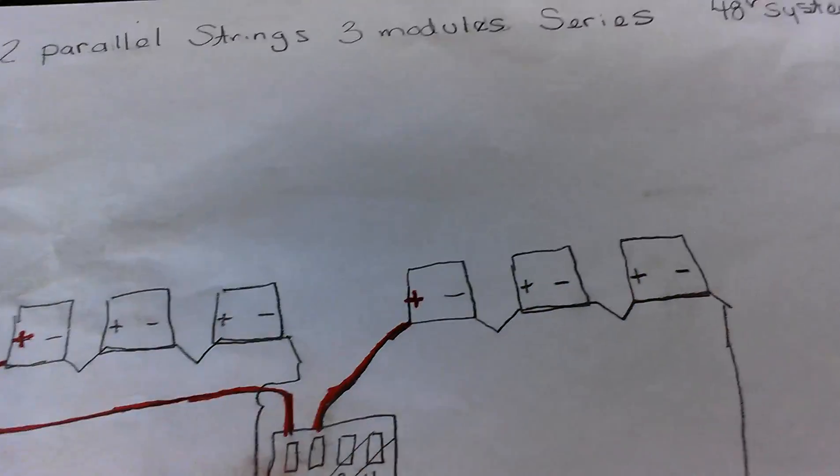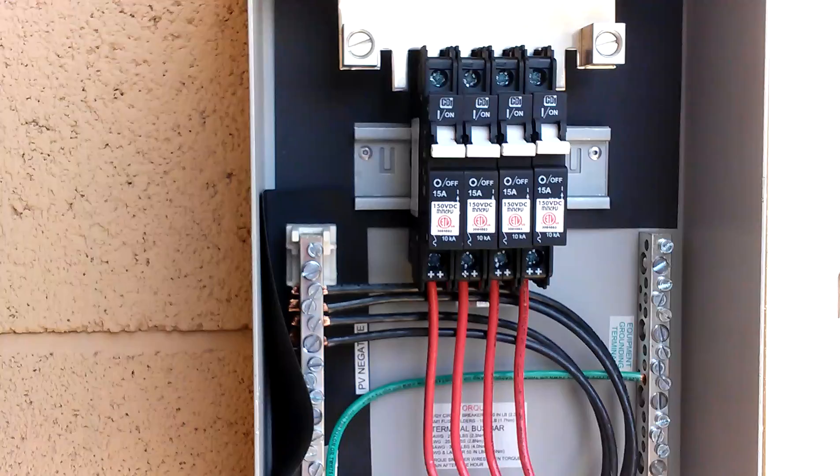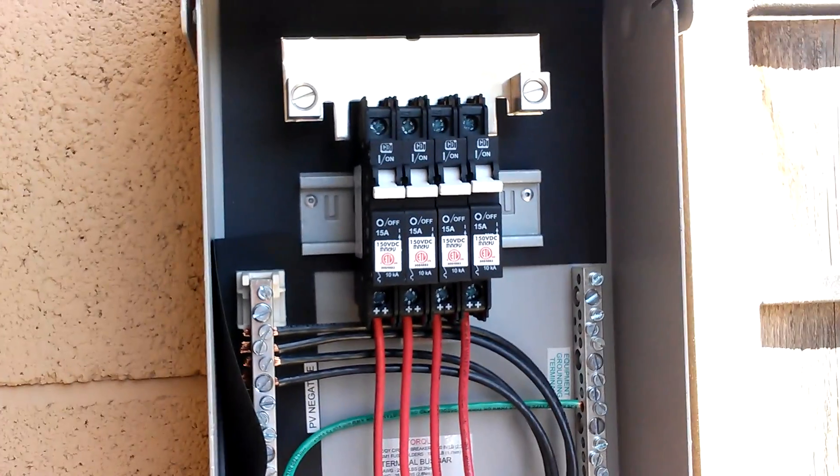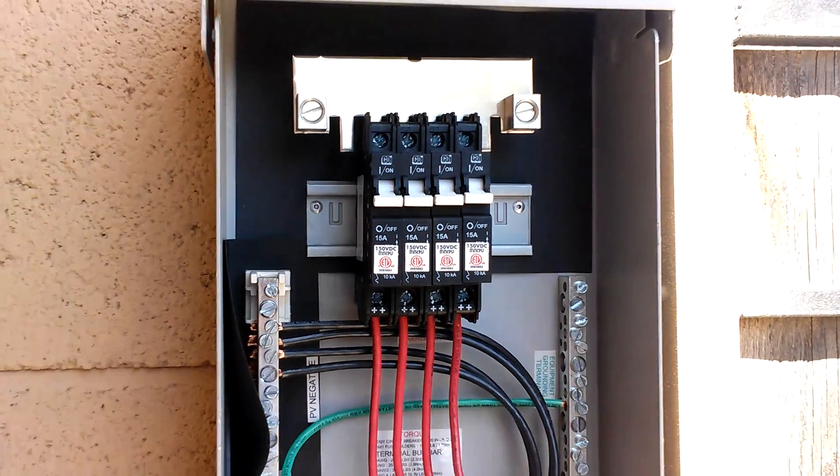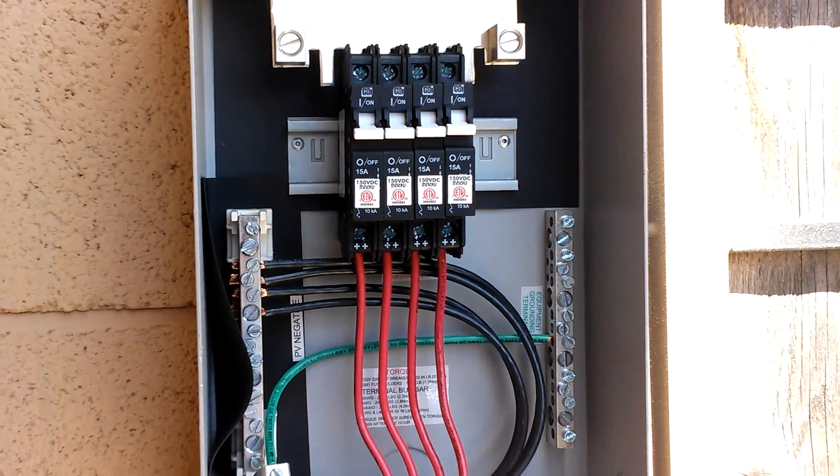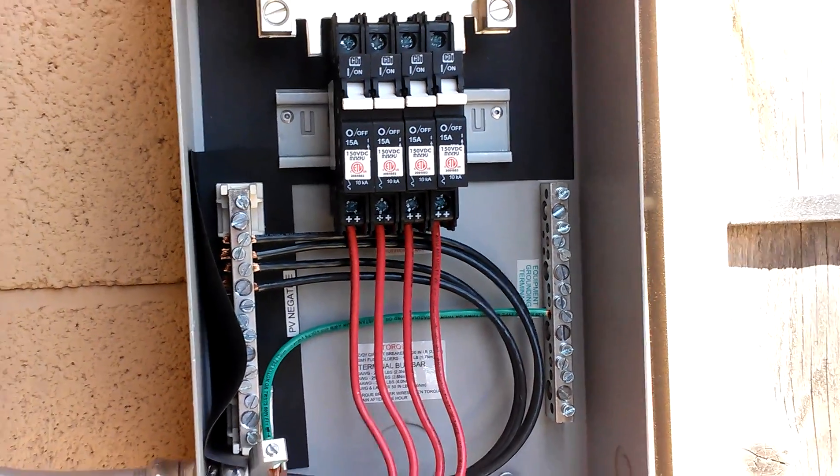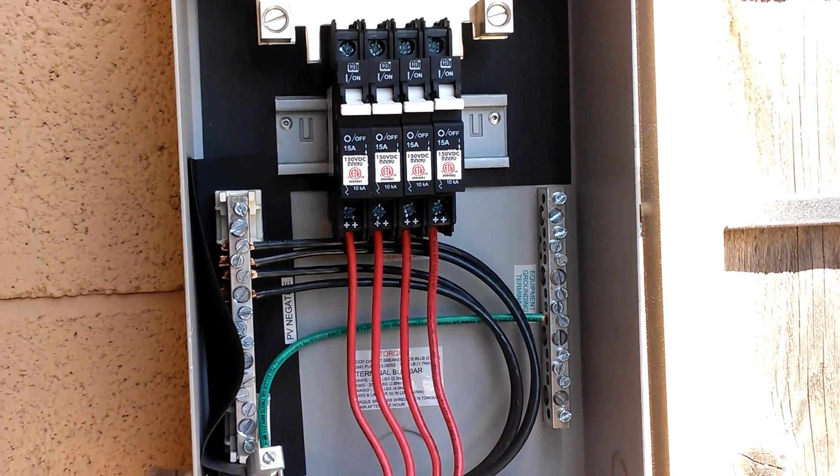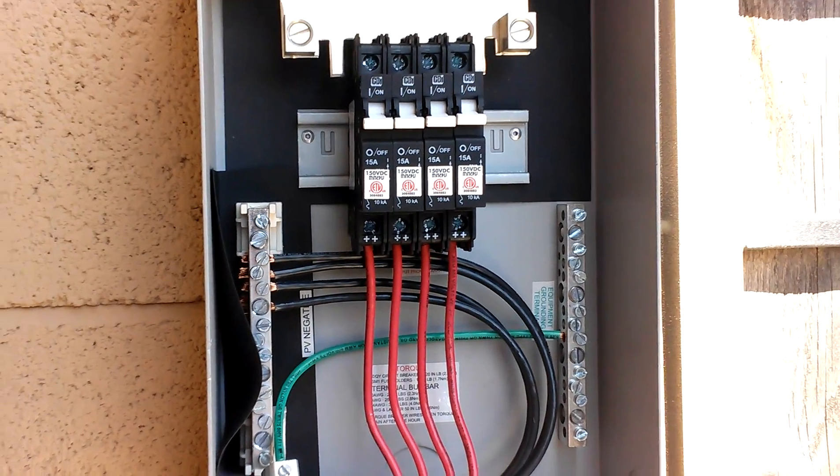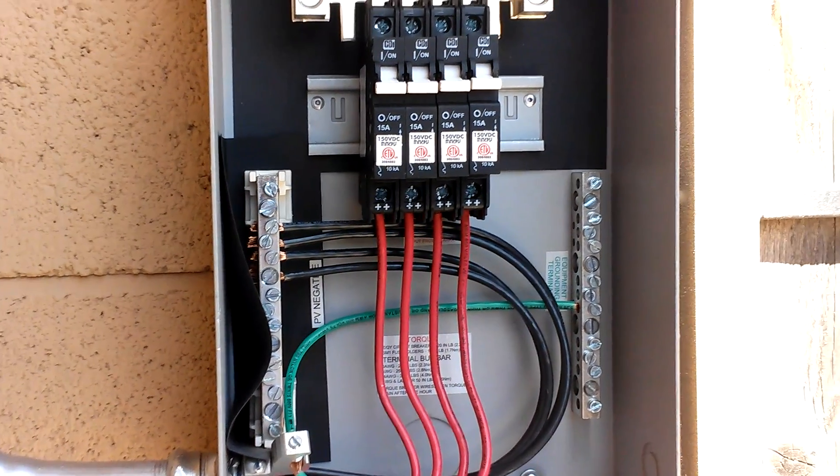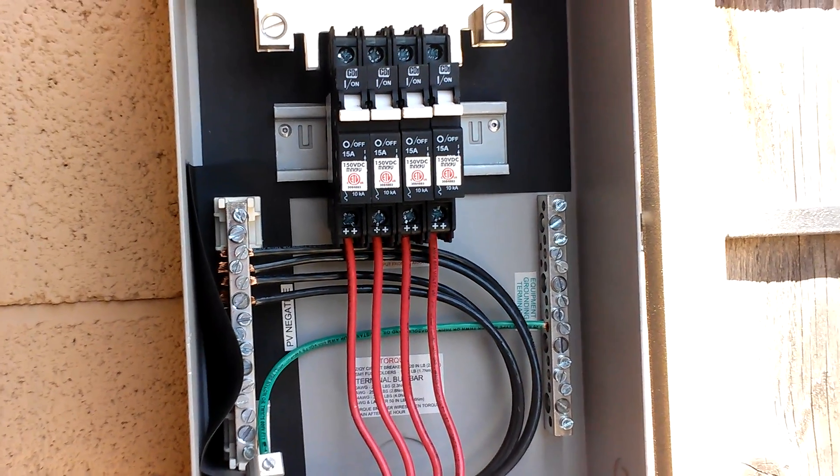Here's the combiner box. Make sure that you get all your numbers correct and get some help if you don't know what's going on, because you will smoke your equipment. You'll burn your charge controller out and charge controllers are fairly expensive. The one I got is the FlexMax 80 which can do up to 80 amps and is over 500 bucks.